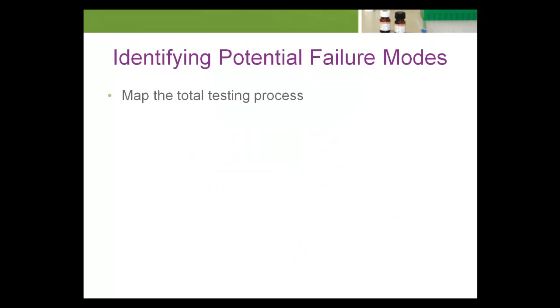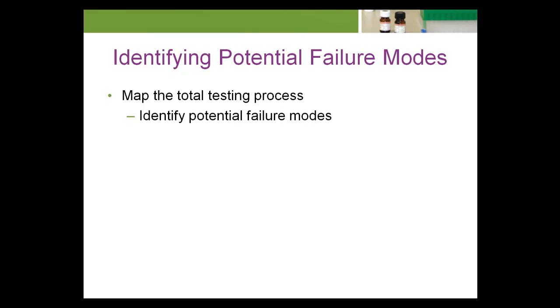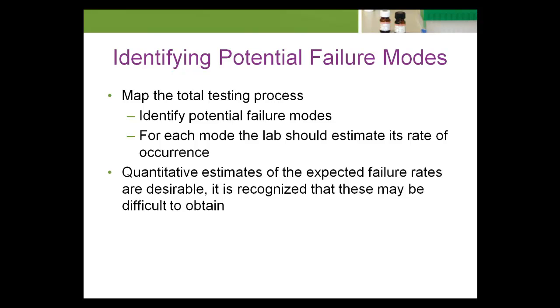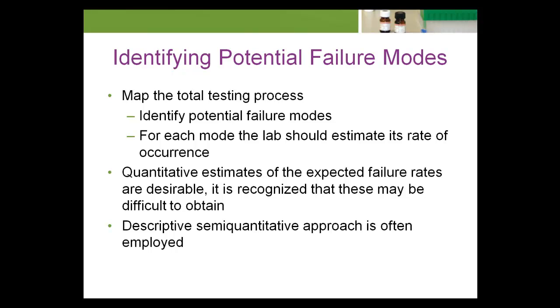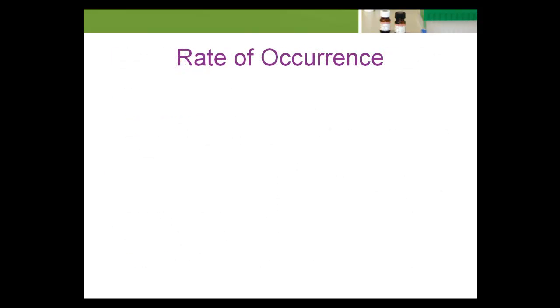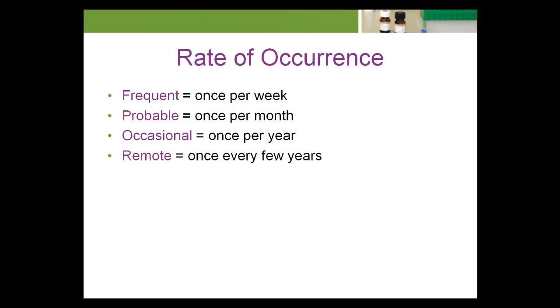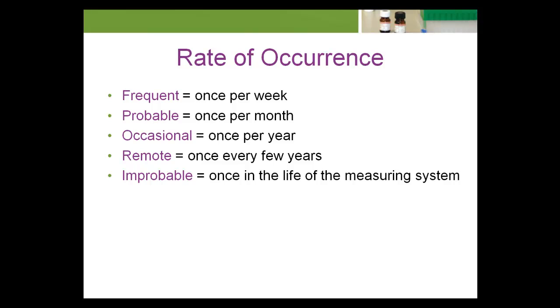The first task is to map the total testing process and identify potential failure modes that could lead to patient harm. For each mode, the lab should estimate its rate of occurrence. While quantitative estimates of the expected failure rates are desirable, a descriptive semi-quantitative approach is often employed. EP23A suggests a five-level categorization: frequent equals once per week, probable equals once per month, occasional equals once per year, remote equals once every few years, and improbable equals once in the life of the measuring system.